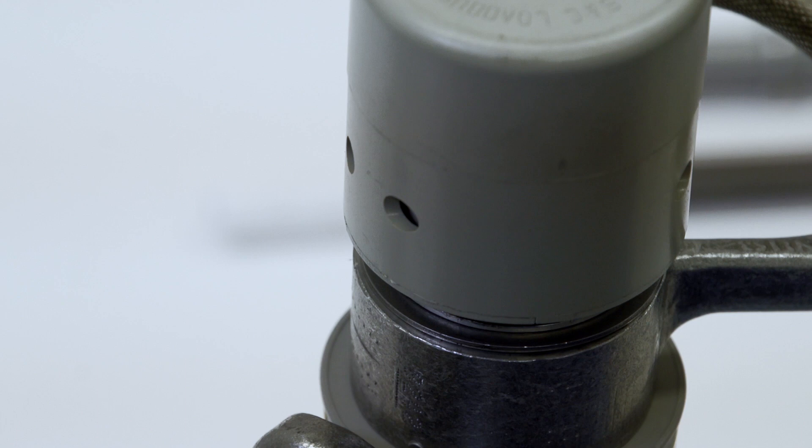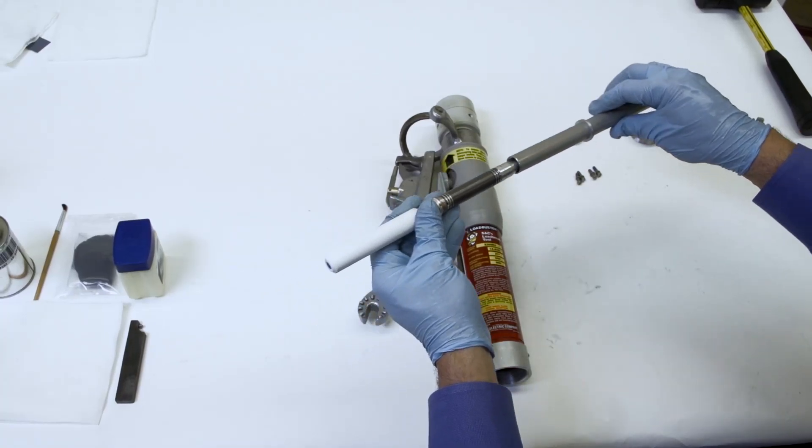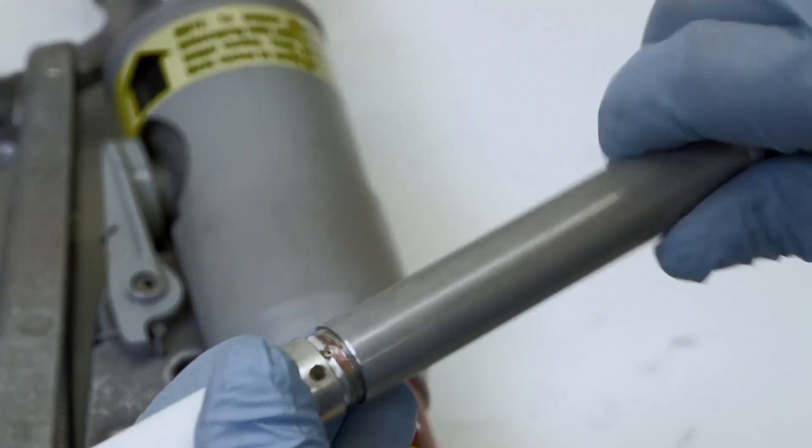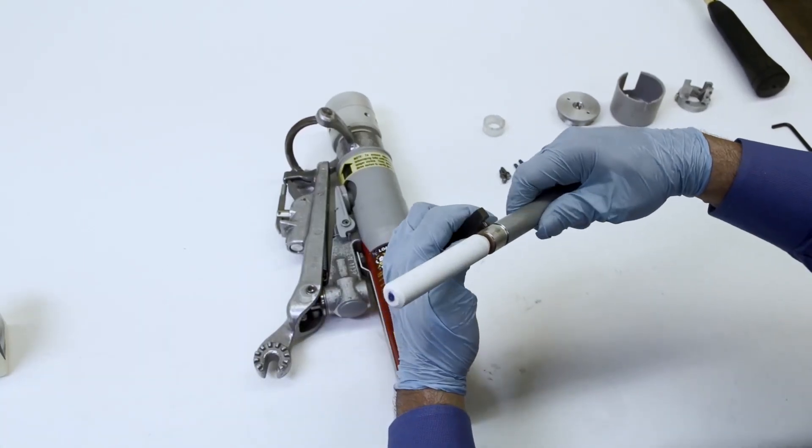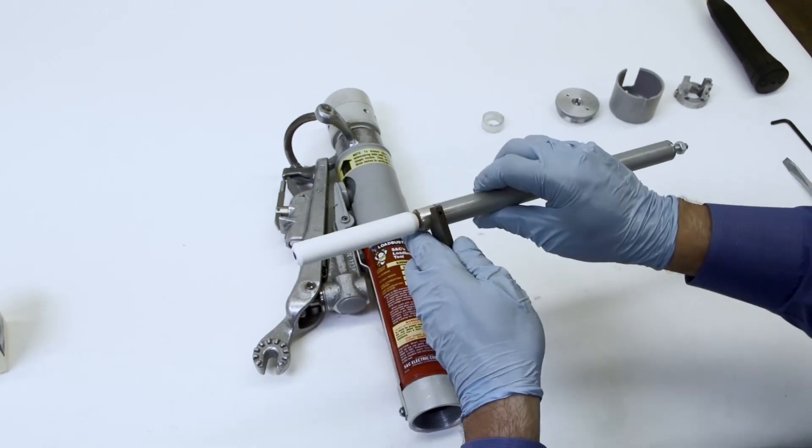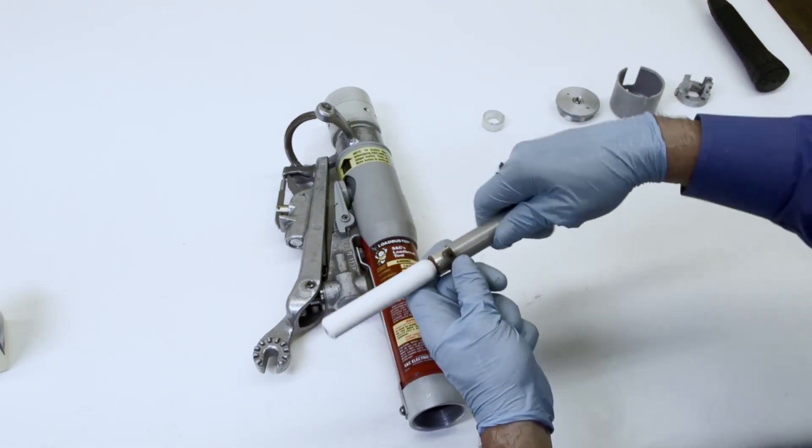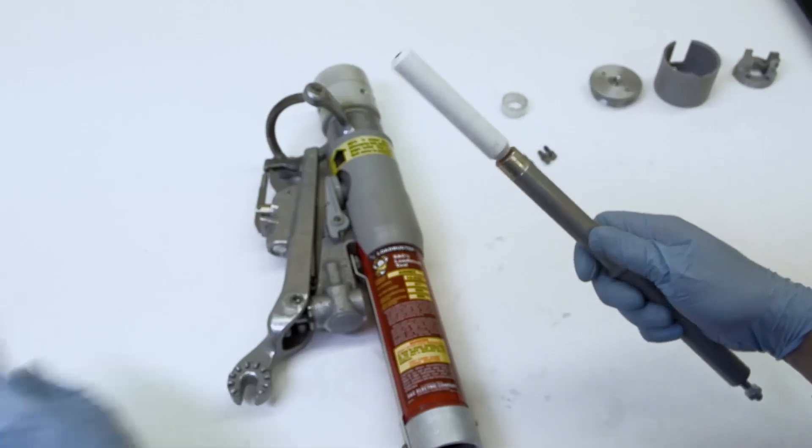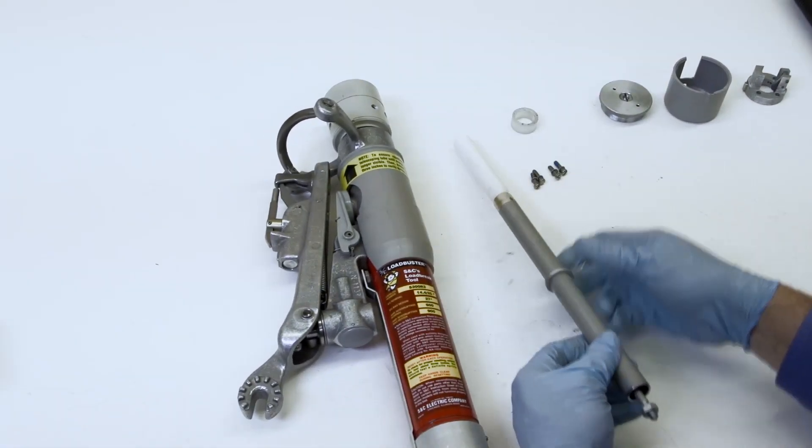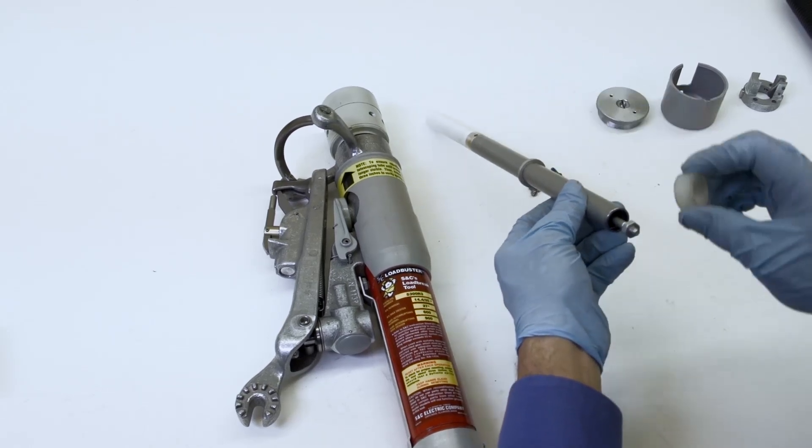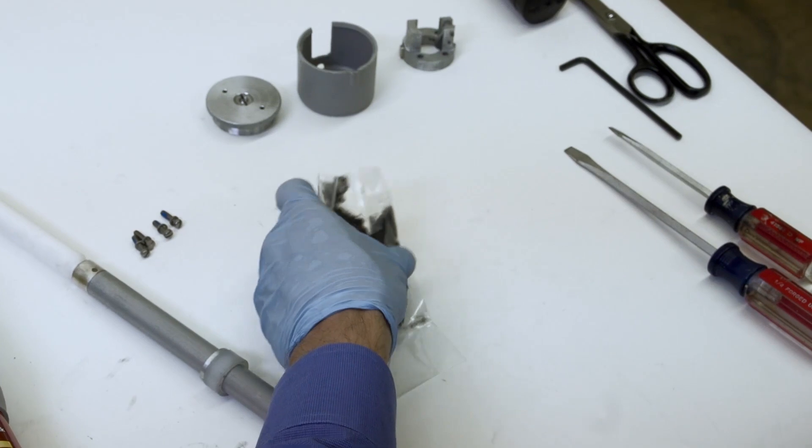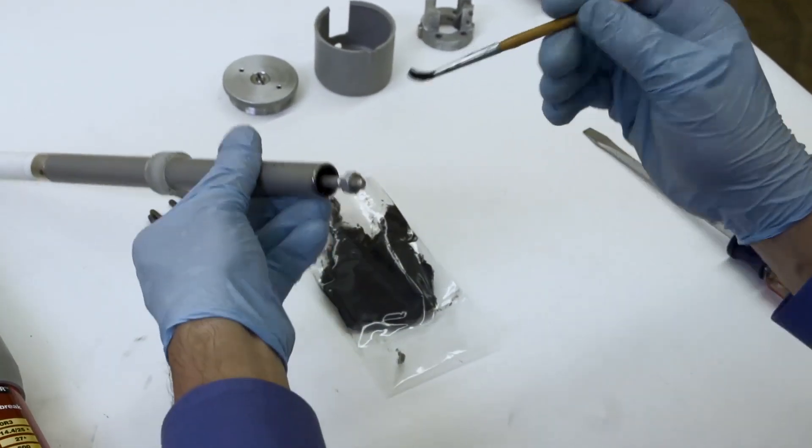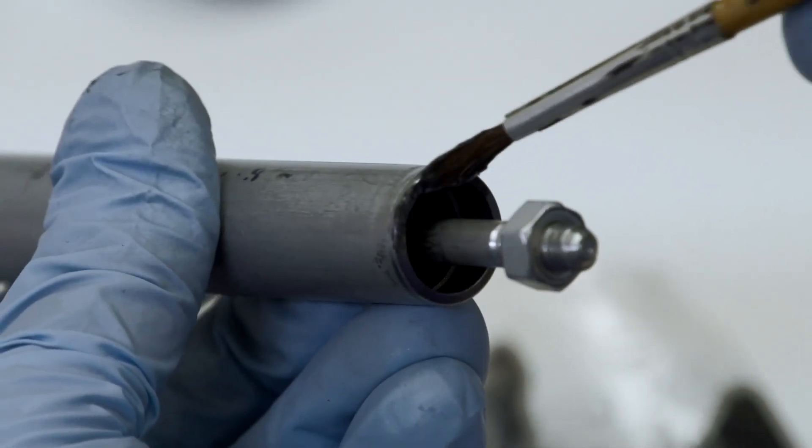Next, screw the contact tube onto the moving contact assembly. Use the S&C spanner wrench to hold the assembly steady while tightening the threads. Then slide the guide bearing over the open end of the contact tube.